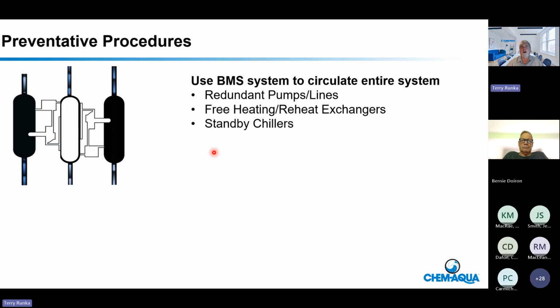When we get a call, Terry, this is the third test in a row where we had it, we killed it, we tested again, it was gone, and now it's back. What we've found, not just me, when we get there, is that the problem is biofilm, and the systems don't circulate all the time. If you've got two chillers, one's running and circulating, and the other one's on standby, not running. Well, if it's not running, even with all the automation, it doesn't get any biocide.